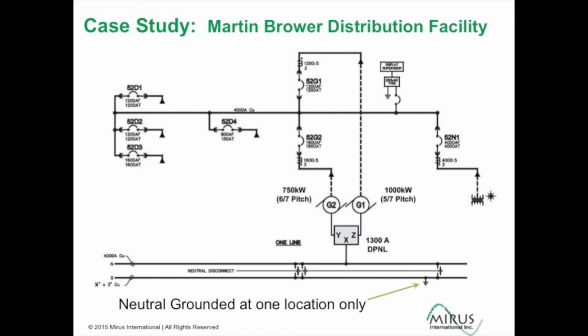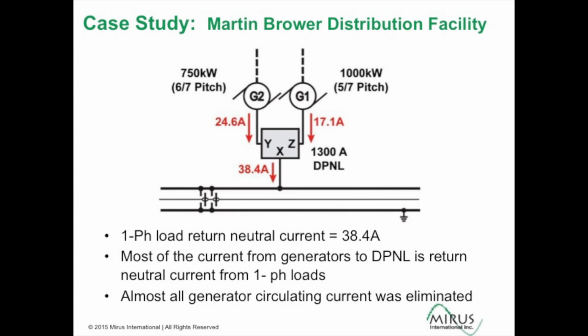And grounding, the system was grounded in just one location at the neutral bus. Once the DPNL was installed, we went back and took measurements. You can see the residual current and the combination of the current from generator 2 and generator 1. If we sum those two currents up, it's about 41 to almost 42 amps. And the current returning to the neutral here is 38 amps. So that difference is only 2 or 3 amps. That's all that's left of residual circulating currents.